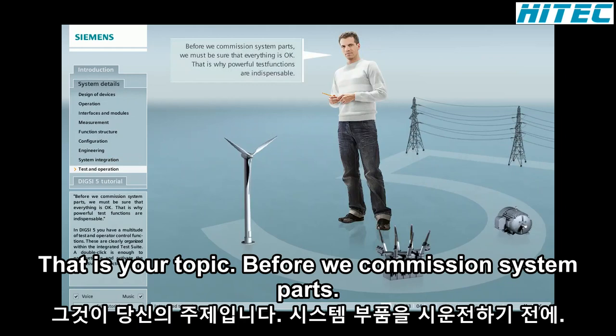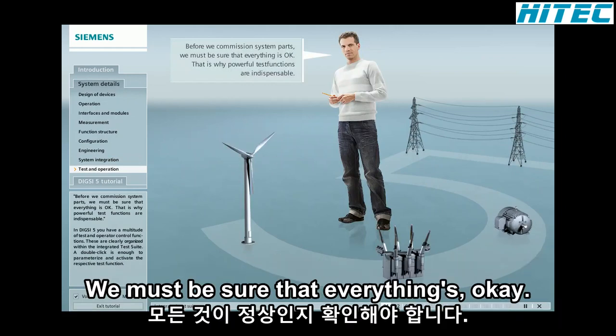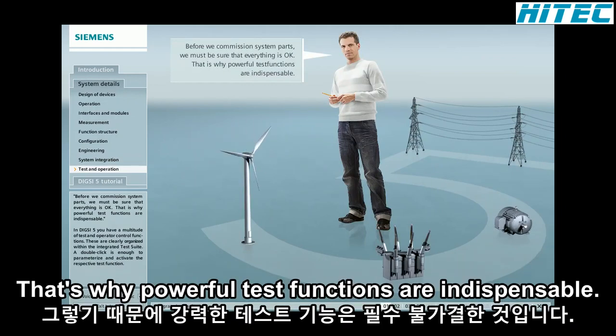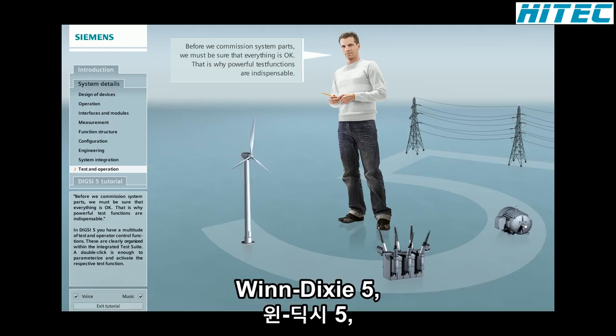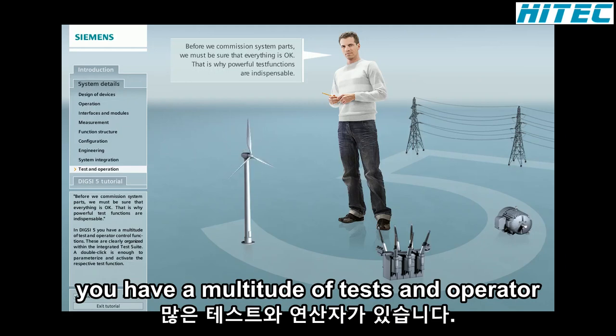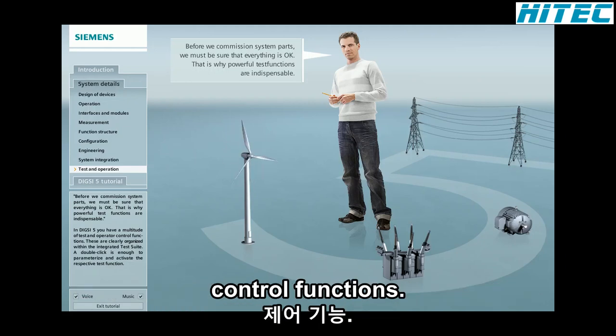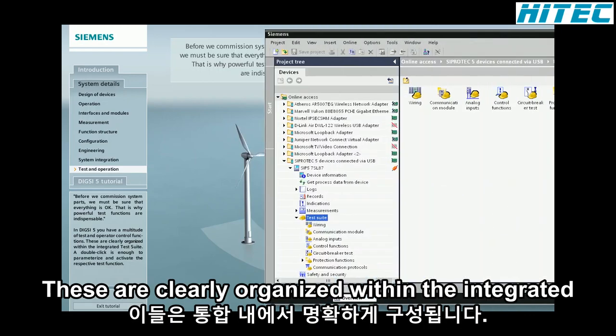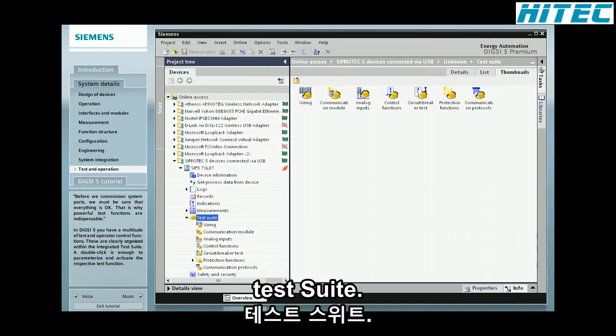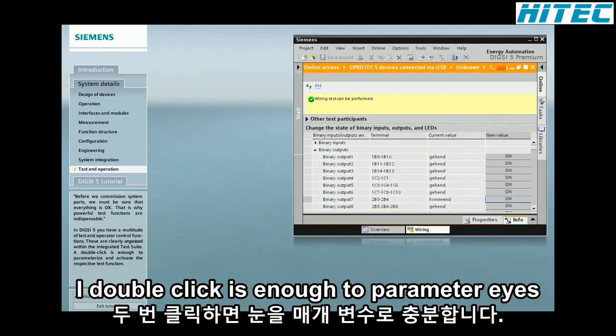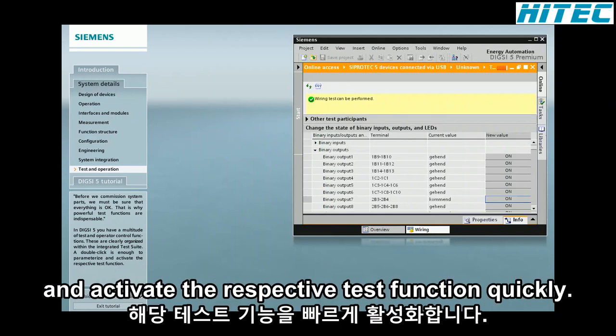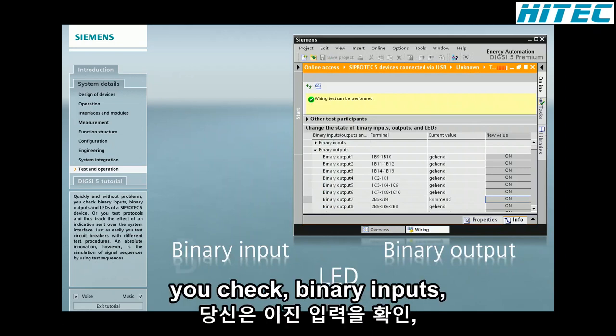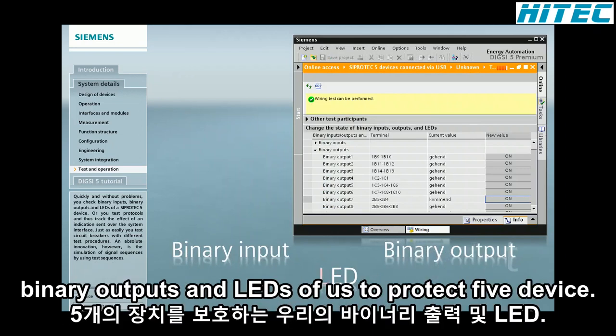Before we commission system parts, we must be sure that everything's okay. That's why powerful test functions are indispensable. In DIGSI 5, you have a multitude of test and operator control functions. These are clearly organized within the integrated test suite. A double click is enough to parameterize and activate the respective test function. Quickly and without problems, you check binary inputs, binary outputs, and LEDs of a SIPROTEC 5 device.